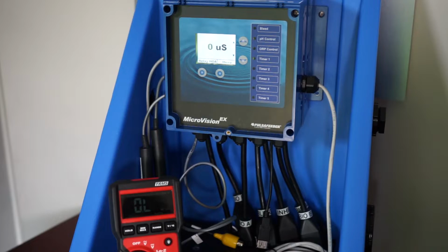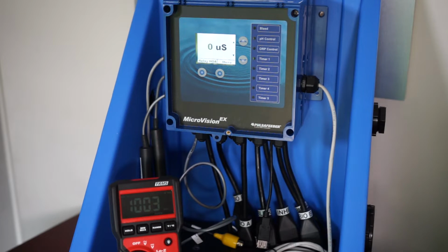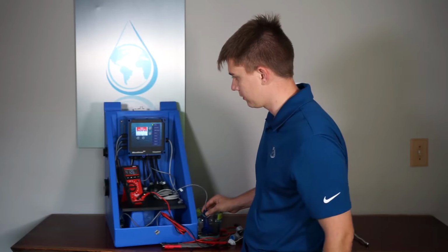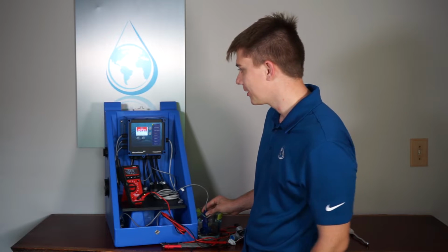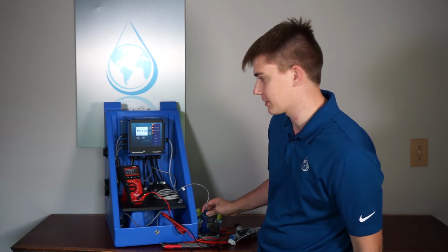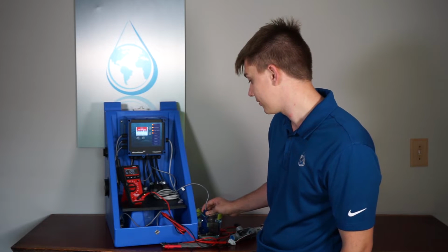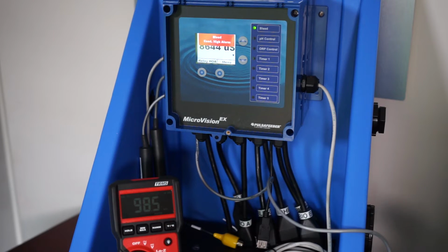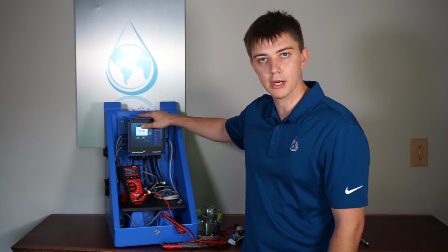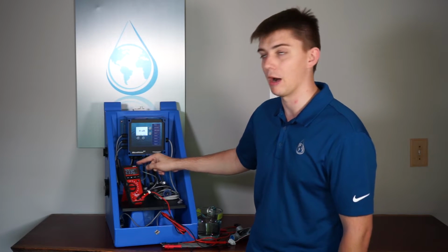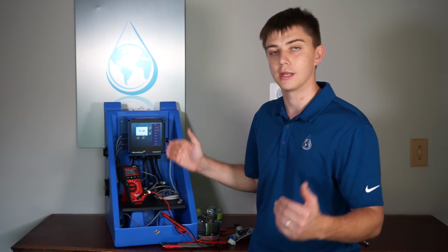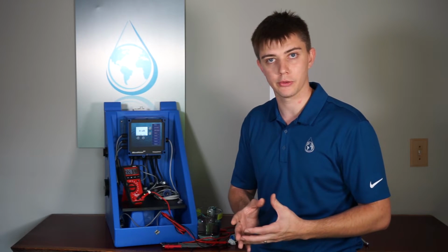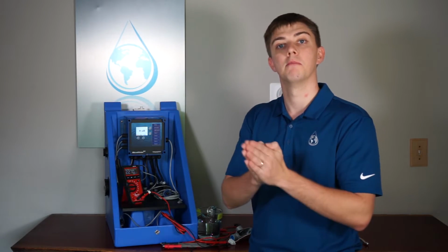So you'll notice my kiloohm value went much lower. And then similarly, if I put my toroidal probe in, you can see it's now spiked almost to 10,000 microsiemens and I'm getting a conductivity high alarm on the controller. So my conductivity on the controller in microsiemens went up by adding the salt, but my resistivity did the opposite. It goes down. More salt in the water makes the solution more conductive.